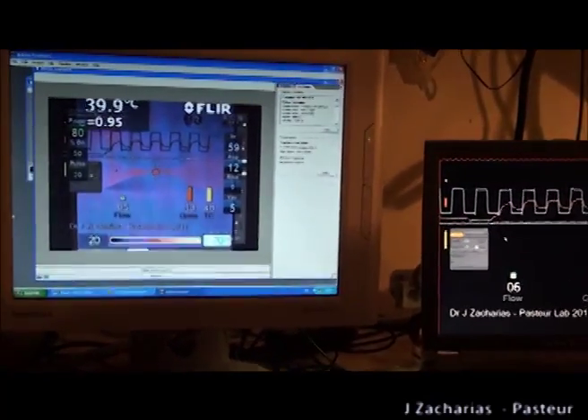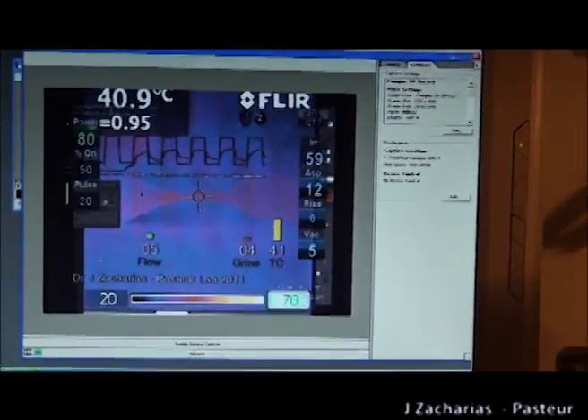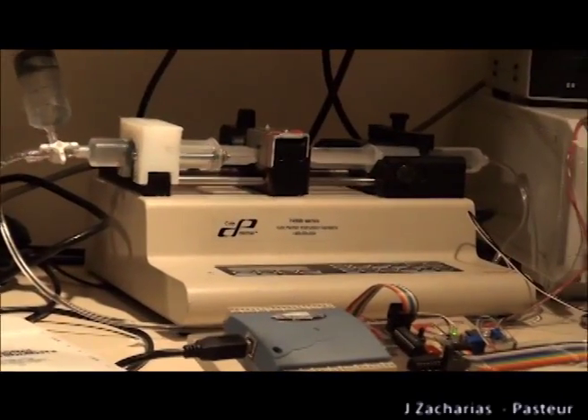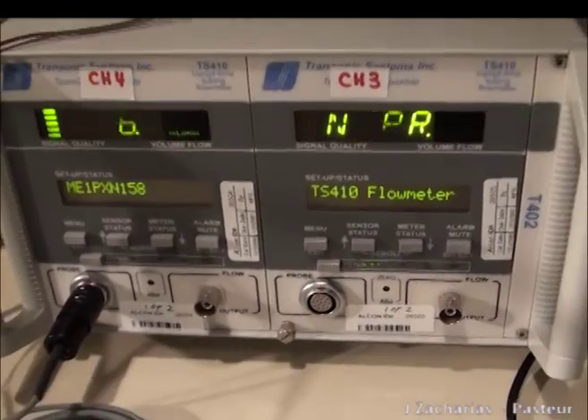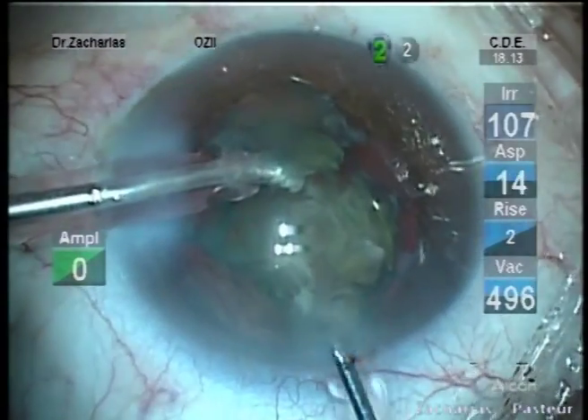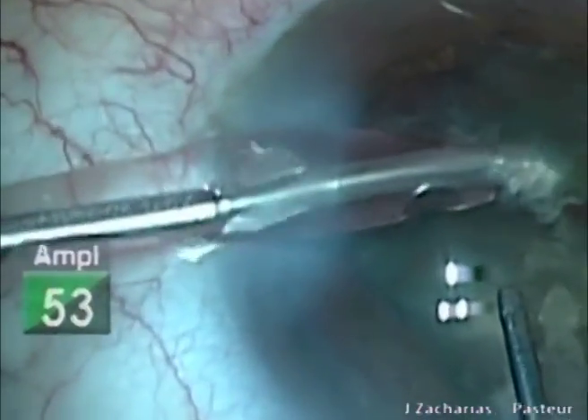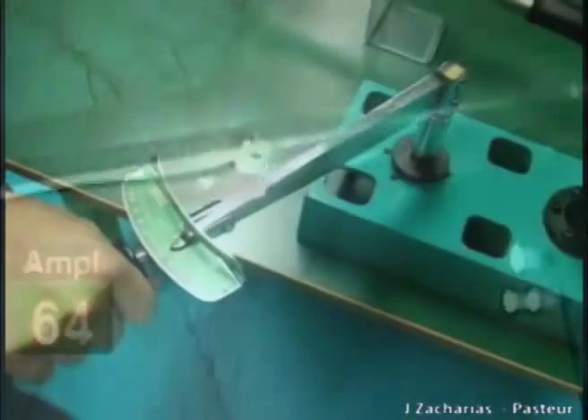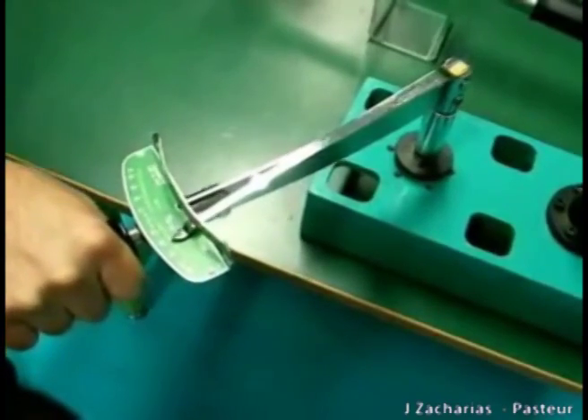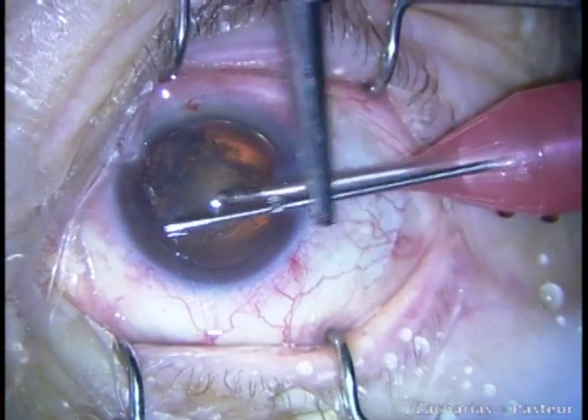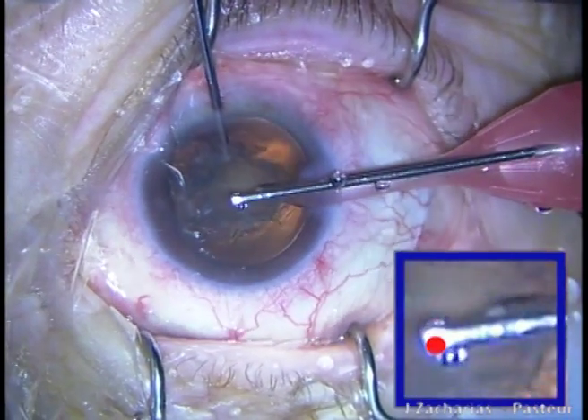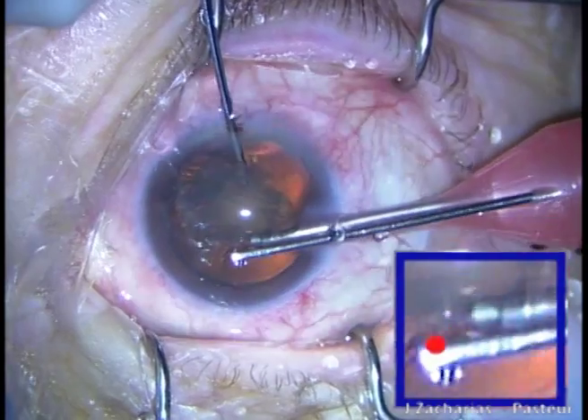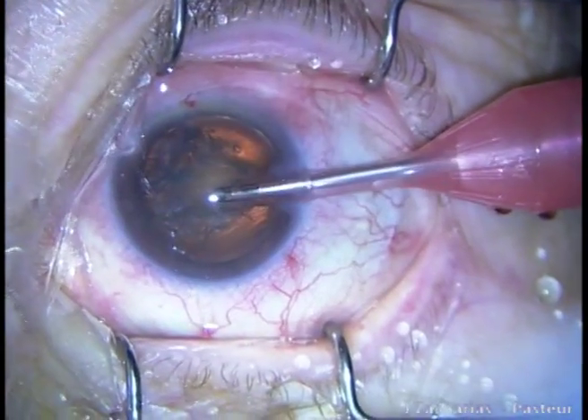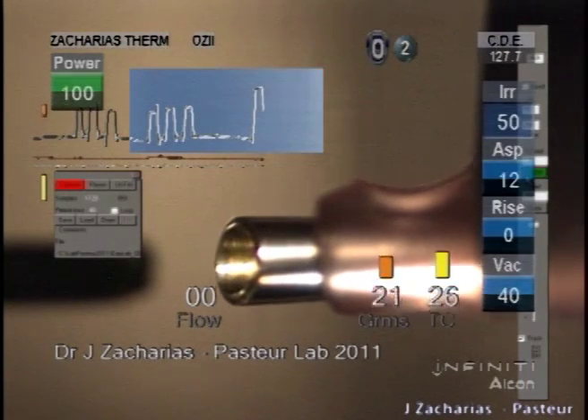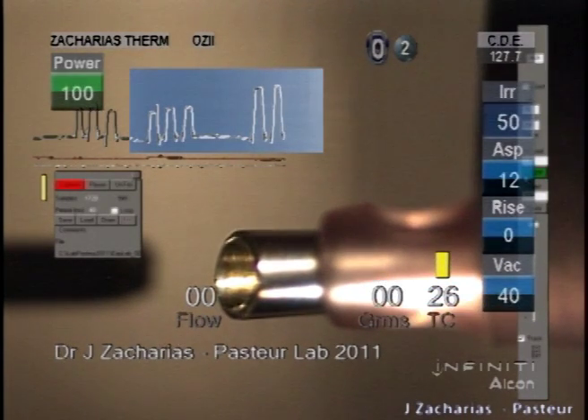The system delivered pulses of compression and relief with precise force and timing. Flow was circulated by a dual syringe pump and was continuously monitored using a flow sensor. We found no references indicating the range of force a surgeon can apply to the walls of an incision during surgery. To find this out, we used the principle of operation of beam torque wrenches. An inactive probe with a reference mark was displaced laterally inside a micro-incision, and the resulting probe lateral deflection was recorded. The probe was then tested in the lab using the force control system. In this way, we obtained an estimation of real incision stress levels, useful for this and future tests.